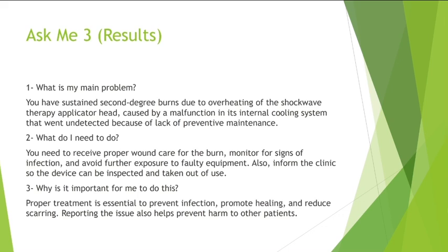Second, what do I need to do? The patient must receive proper burn care, monitoring the wound for signs of infection, and avoid using a faulty machine again. The incident also needs to be reported to the clinic so the equipment can be removed and inspected.